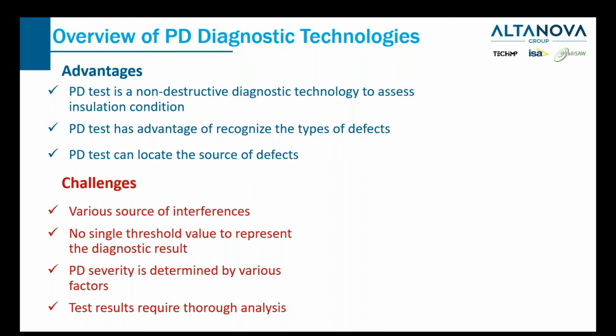The reason we cannot use a single threshold value to present the result is that PD severity is determined by various factors. A very important factor, first, is what type of discharge we're talking about.